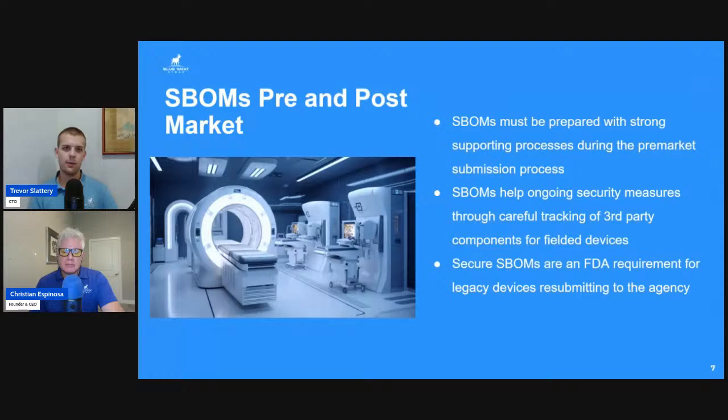When we're tracking an SBOM carefully and we're tracking the components within the SBOM carefully, we can set up checks to identify when there are changes to that component. If we see that there's no activity in a certain package for a year, 2 years, it may be the case that it's no longer supported and requires a little bit more proactive research into what is going on. Is there a need for us to replace the component, or should we just monitor it a little bit more carefully in the case there is a vulnerability discovered? Regardless of what the outcome is, it's a clear indication that something needs to be done about that component. At a minimum, there should be some increased monitoring around it.